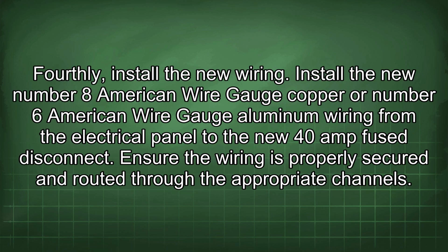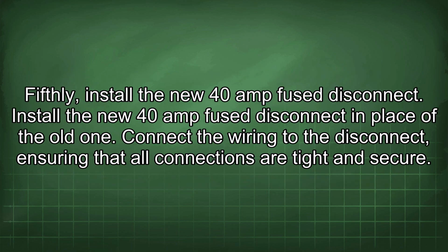Fourthly, install the new wiring. Install the new number 8 American wire gauge copper or number 6 American wire gauge aluminum wiring from the electrical panel to the new 40 amp fused disconnect. Ensure the wiring is properly secured and routed through the appropriate channels. Fifthly, install the new 40 amp fused disconnect. Install the new 40 amp fused disconnect in place of the old one. Connect the wiring to the disconnect, ensuring that all connections are tight and secure.